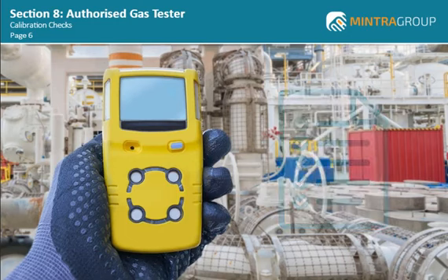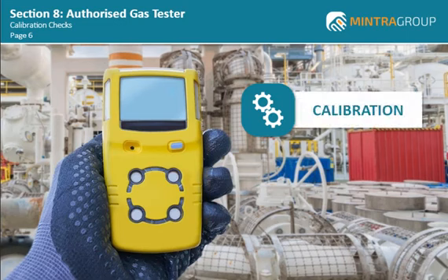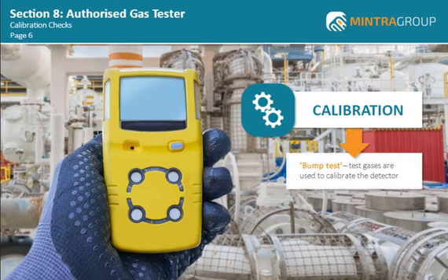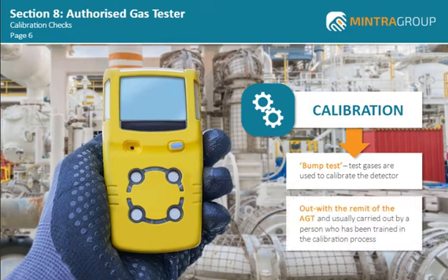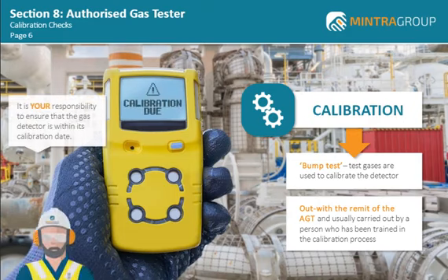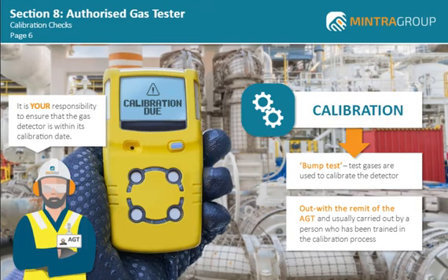Firstly, all gas detectors require calibration to ensure that the results recorded are true. This is done by what is known as the bump test, and test gases are used to calibrate the detector. Calibrating gas detectors is normally out with the remit of the AGT, and is usually carried out by a person who has been trained in the calibration process. Most modern gas detectors will indicate on the screen when the next calibration is due. It is your responsibility to ensure that the gas detector is within its calibration date.